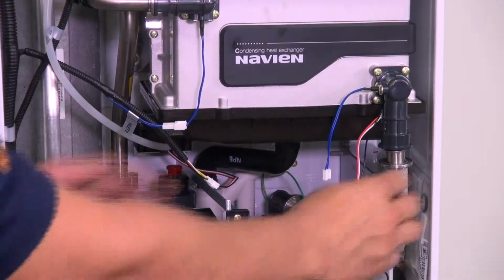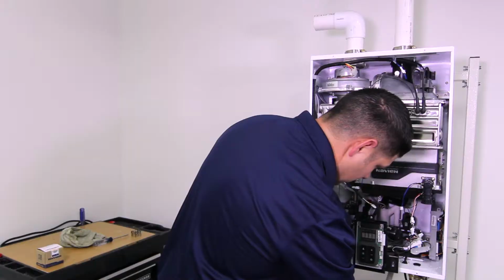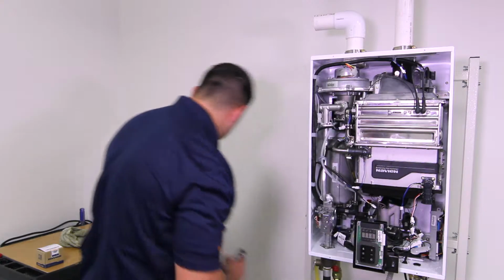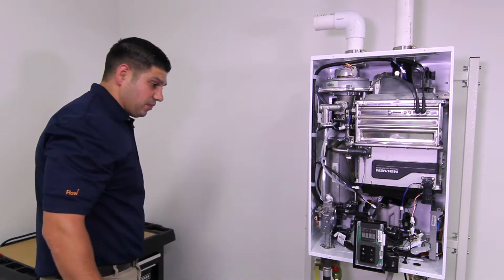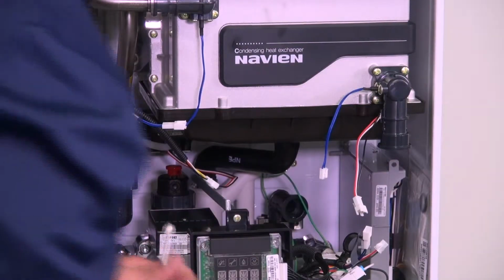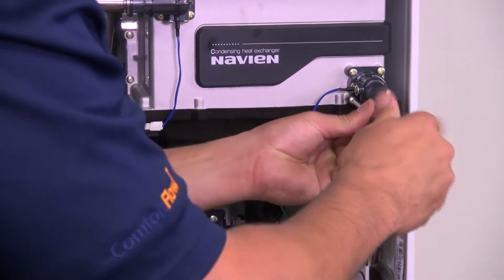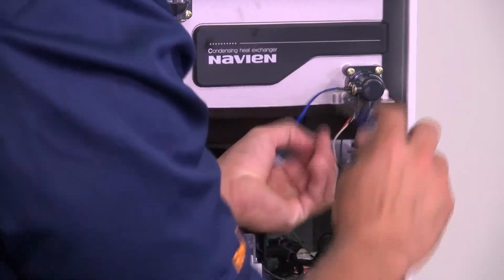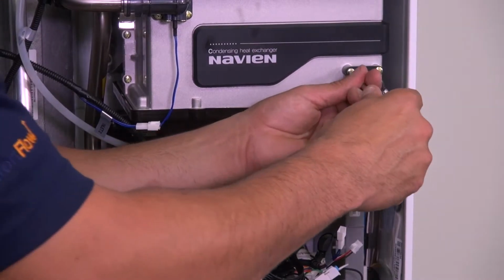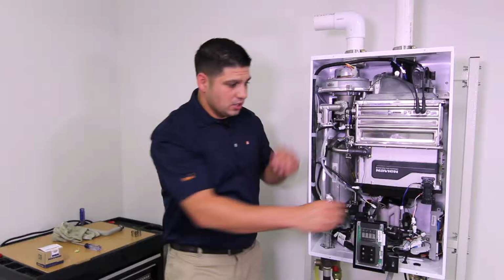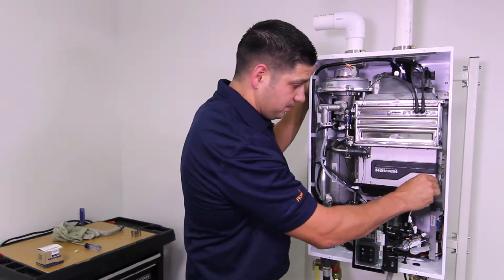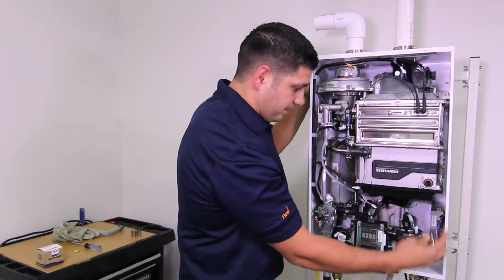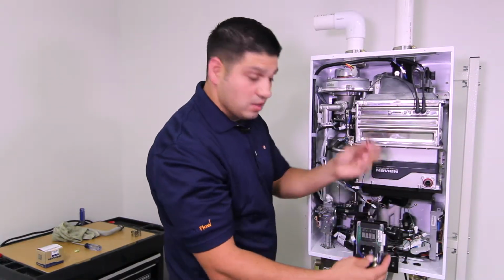And we're going to just pull out your inlet pipe. You may have a little bit of water that spills down. This is where your bucket and your rag comes into play. We got our inlet pipe removed. We're going to take off our flow sensor. So you have 4 screws holding on your flow sensor to your secondary heat exchanger. So when you remove your flow sensor, you're going to have your O-ring.